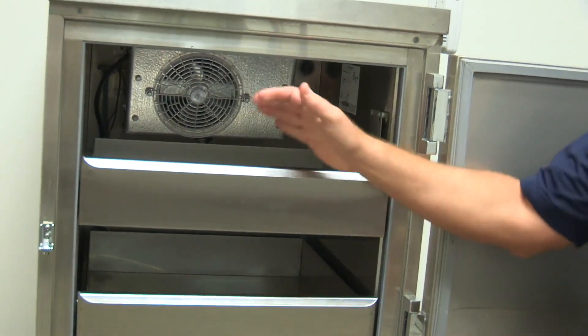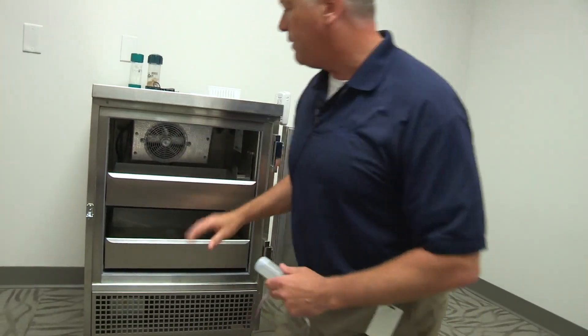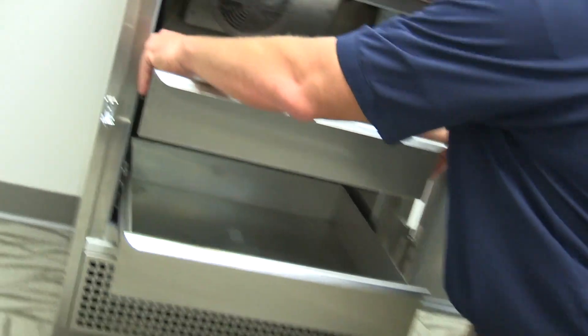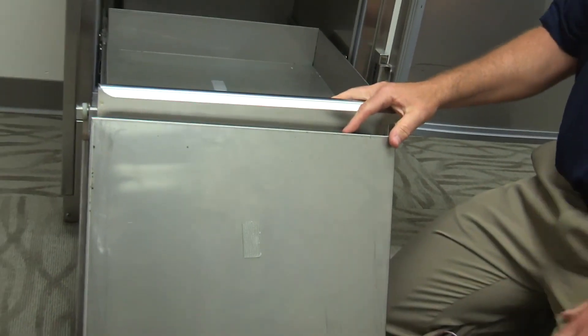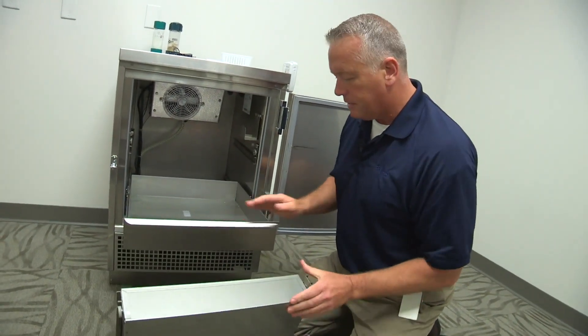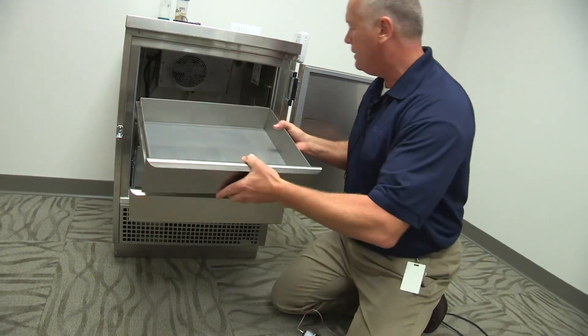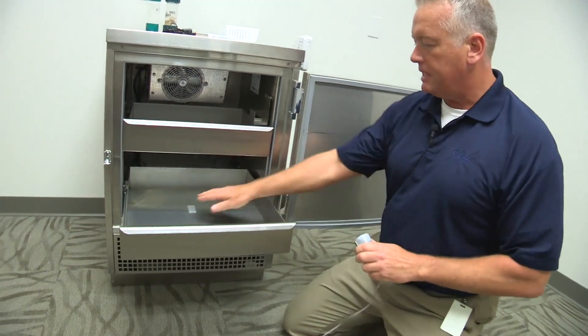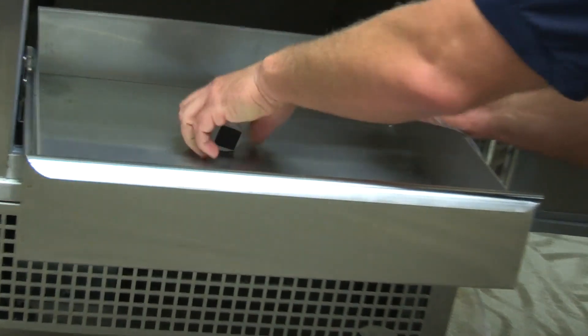You don't want direct contact or access to the fan or the cooling piece. I've scoped out two areas: one on the bottom shelf and another underneath the shelf as I pull it out. I could place the probe on the bottom. I've put the opposite piece of Velcro on the shelf and one right on the bottle, and I'm going to place that probe and thermal buffer right on there. You can put anything else you want around that piece.